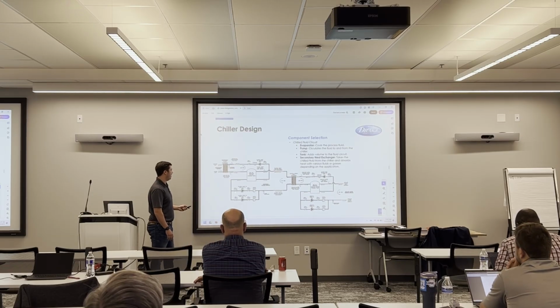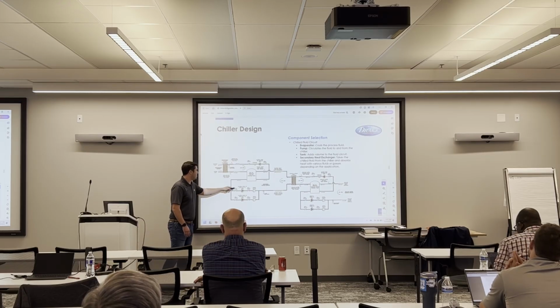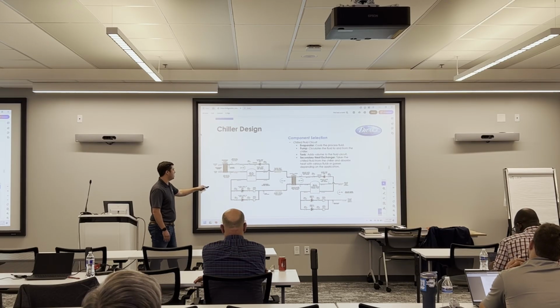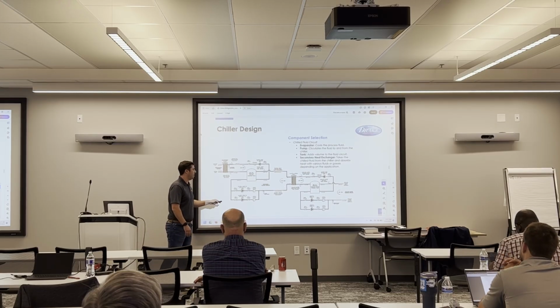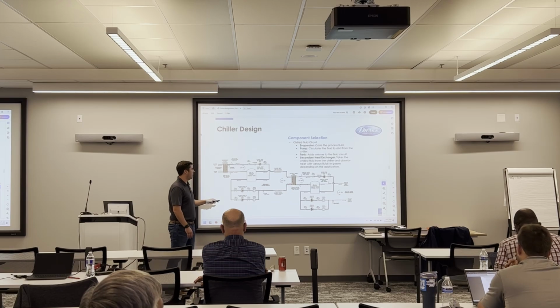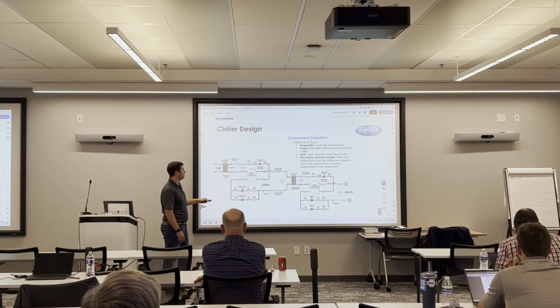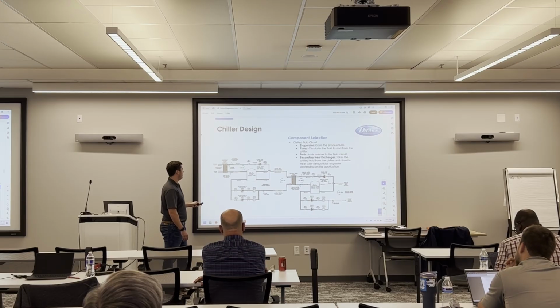And then, again, in this example, we have a separate process loop. So we have glycol pumps pulling off the same 300-gallon tank. It's sending fluid to that secondary heat exchanger. That fluid's going to absorb heat from the other side of the heat exchanger and send it back to the tank. So essentially we have what I call a recirculating pump. It's just recirculating the fluid from the tank to the chiller, just to keep the tank cold. And then these are glycol process pumps, sending fluid from the same tank to the heat exchanger to cool a secondary process loop.